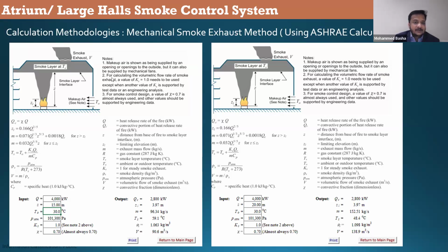They have mentioned here the number 2. For calculating the volumetric flow rate of smoke exhaust, a value of Ks1 needs to be used, except when other values are supported by test data or an engineering analysis. So normally it's 1. X is 0.70. For smoke control design, a value of X, which is the convective fraction, dimensionless, is almost always used. Any other value should be supported by engineering data.